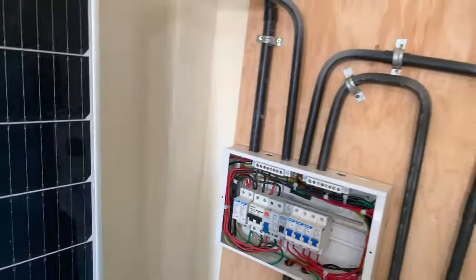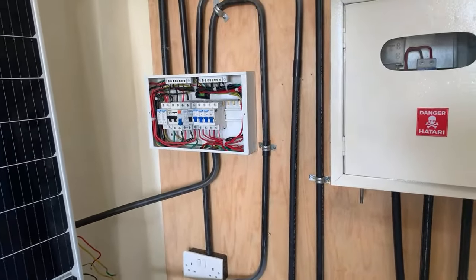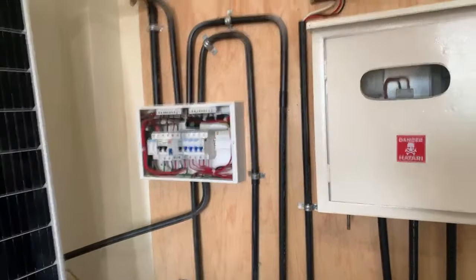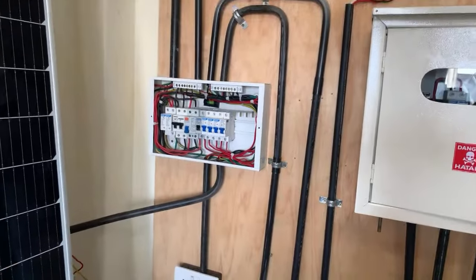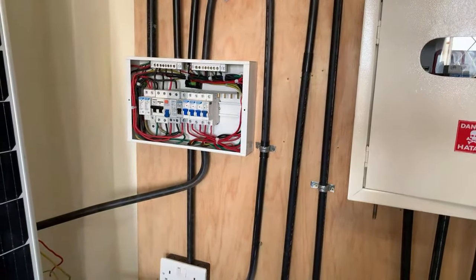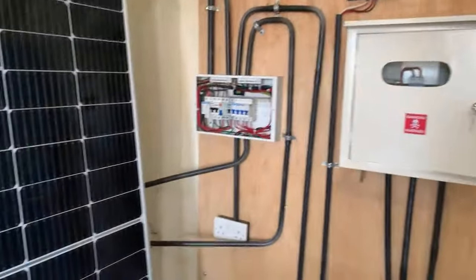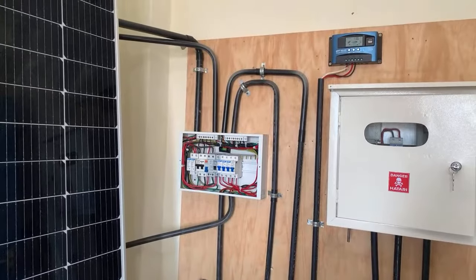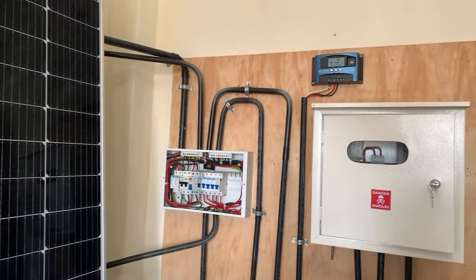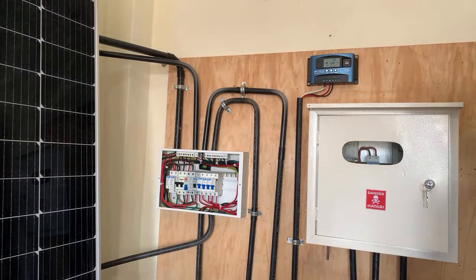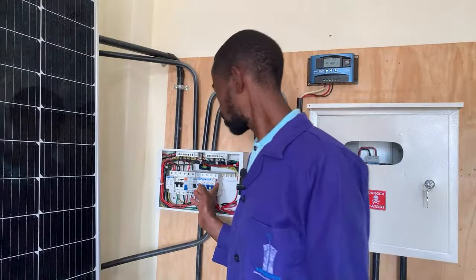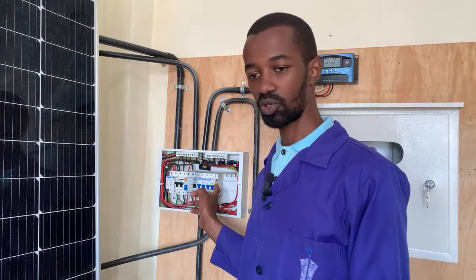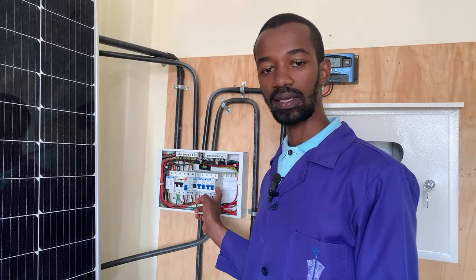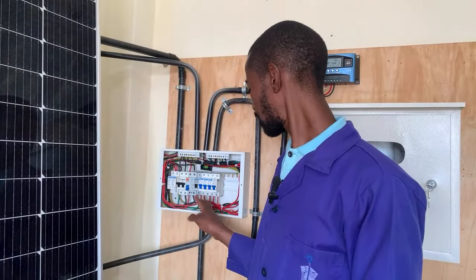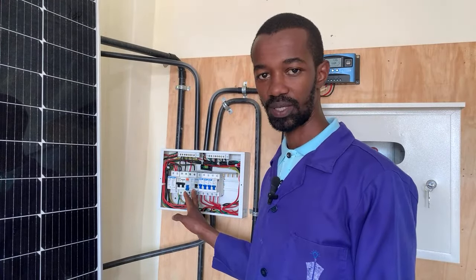So let me just get into the faults, the common faults that may occur there. If you have a fault on a specific MCB, then the question becomes, how do you go about it? In fact, for you to point out that indeed there is a fault on this consumer unit, how will you know? The number one indicator that there is a fault is if there is any device that has tripped here.